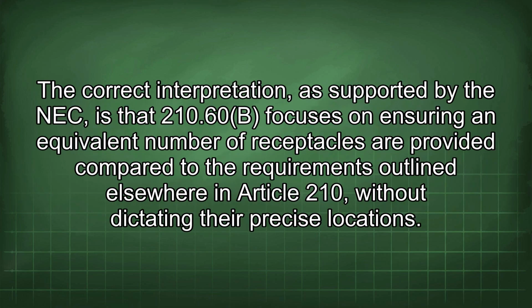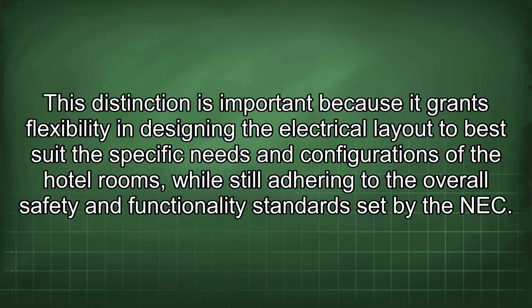The correct interpretation, as supported by the NEC, is that 210.60b focuses on ensuring an equivalent number of receptacles are provided compared to the requirements outlined elsewhere in Article 210, without dictating their precise locations. This distinction is important because it grants flexibility in designing the electrical layout to best suit the specific needs and configurations of the hotel rooms, while still adhering to the overall safety and functionality standards set by the NEC.